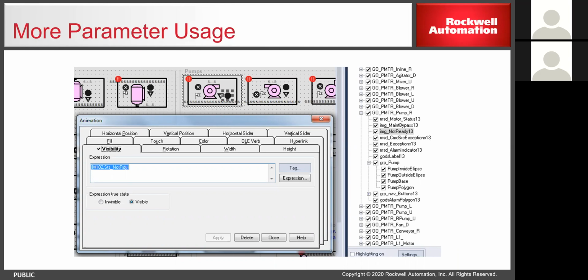So every time you want to add an element here, you just go create your display object, you put it in here and embed it inside of this group. And then you just go in and set all of your tags that you want to use. But instead of using the first part of the tag where you're actually looking at a direct PLC or controller reference tag, you take the front part of that off and replace it with this #102 or #105 or whichever one you make.